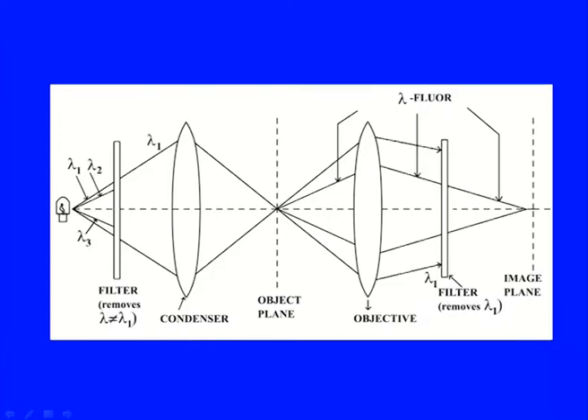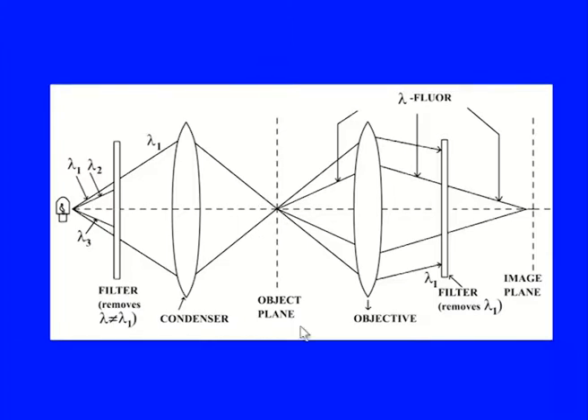Here is a simple schematic of the optics of a fluorescence microscope. The light source is different from a halogen lamp — it could be a xenon arc lamp or mercury vapor lamp. The light passes through the first optical filter, which allows only one monochromatic wavelength to pass through. This is then passed on to the condenser, which focuses the wavelength onto the specimen plane. The object must contain a fluorescent substance that can be excited by this wavelength and emit fluorescence.